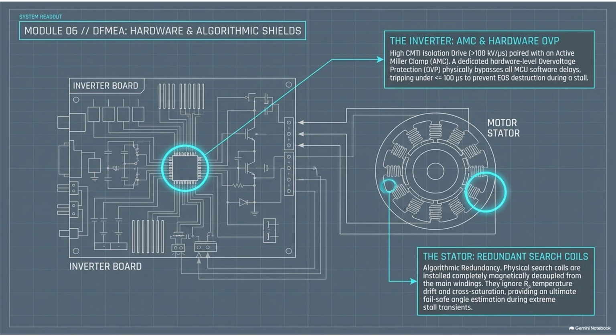Even in the middle of a chaotic high-power electromagnetic stall, where the main sensors are feeding garbage data to the computer, these isolated search coils can independently track the exact angle of the rotor by measuring tiny induced voltages. They feed that undeniable physical truth back to the system, allowing the FOC math to resynchronize and recover the motor. It is like navigating a ship by the stars when your GPS system goes down. The stars aren't affected by cell towers crashing or software bugs. They are a physical constant.